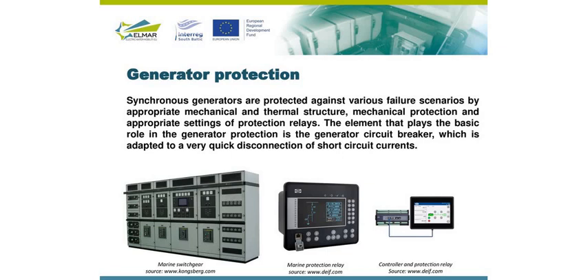Generator protection. So the synchronous generators are protected against various failure scenarios by appropriate mechanical and thermal structure, mechanical protection and appropriate settings of protection relays. The element that plays the basic role in the generator protection is the generator circuit breaker, which is adapted to very quick disconnection of the short circuit current. In this photo we can see a marine switchgear with generator circuit breakers, 4 circuit breakers. We can also see some control panel. On the right side we see a marine protection relay, and a controller also with some protection features.